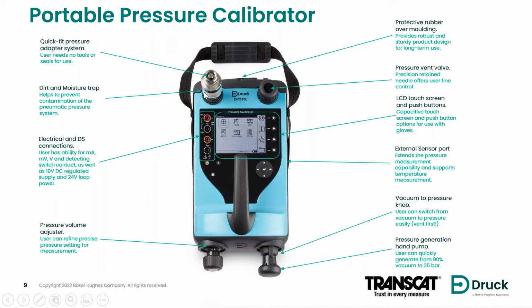Yep. So we have our test port. This is where you would connect your device under test or unit under test. We have pictured here a dirt moisture trap, which we recommend the use of to prevent any of the process materials from the device you're testing getting into the unit itself. We have electronic interconnects for powering up and measuring the output of devices. Down at the bottom here, we have our pressure pump built into the unit for generation of pressure to the test port. So we have a gross pump on this side, and then a volume adjuster for fine adjustment on this side. And we also have a selector switch where you can reverse the stroke of the pump to generate vacuum. On the side, which you can't see in this picture, there's a connection for external remote pressure sensors for expanding the pressure range capability.